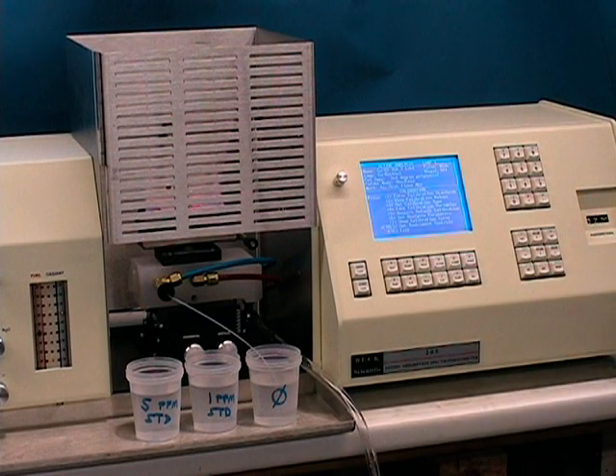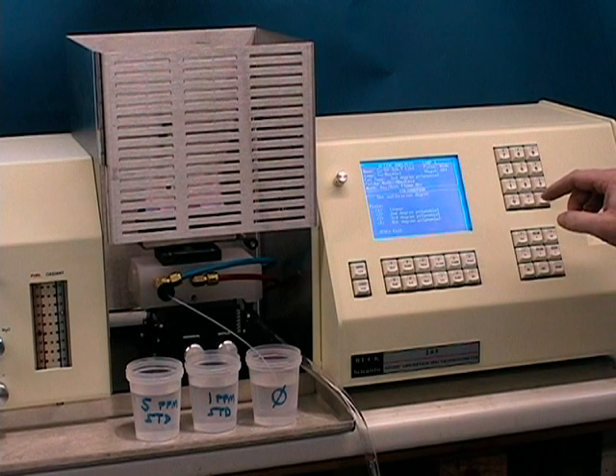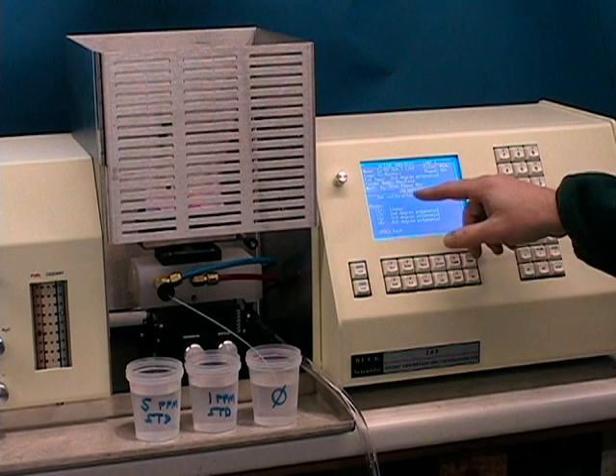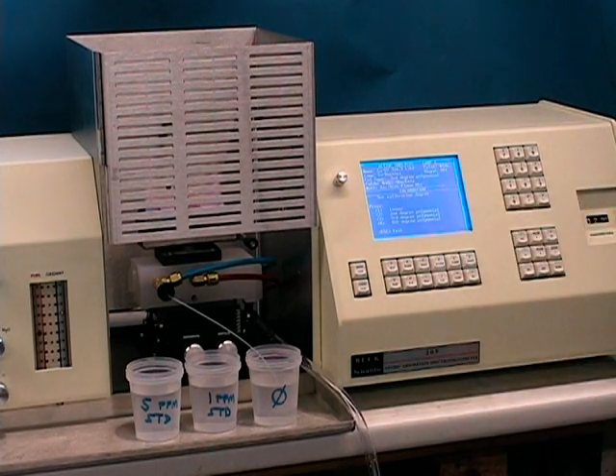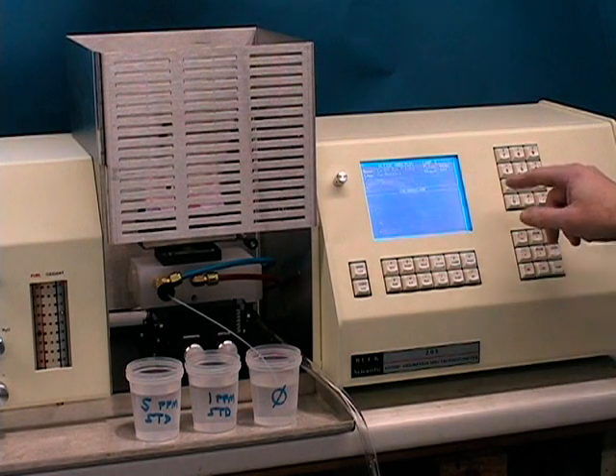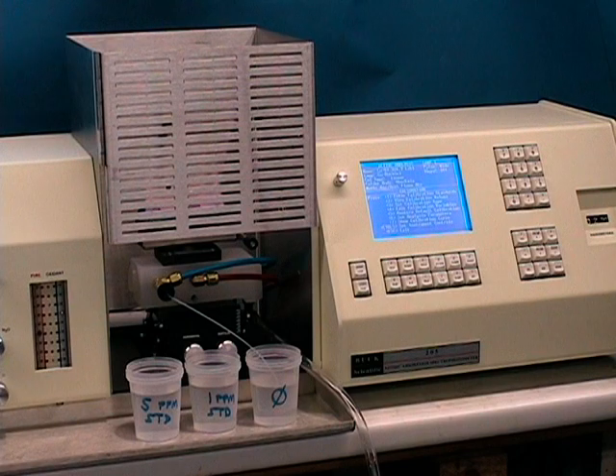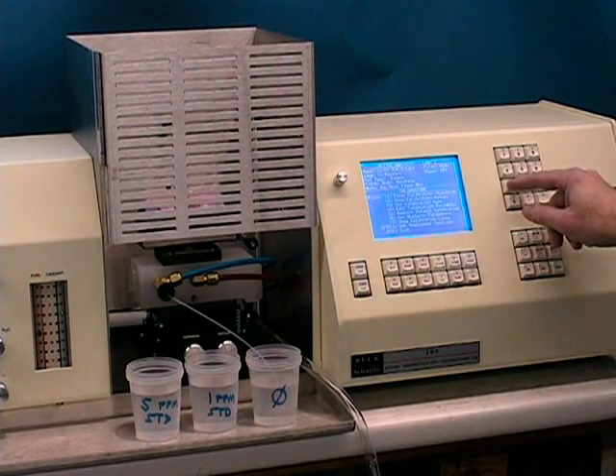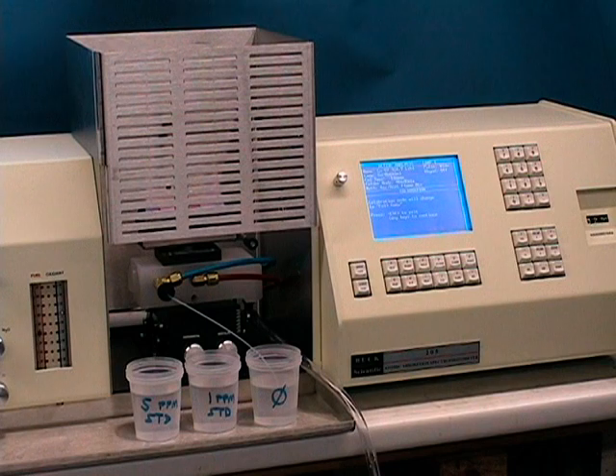And for a new analysis, the default has a third order cubic calibration curve, which is not useful. So press option 3 and select either a first order linear or a second order quadratic if you have multiple standards. Linear and first order and quadratic second order are acceptable for most government and analytical work. Then you will press option 1 to select your calibration values.